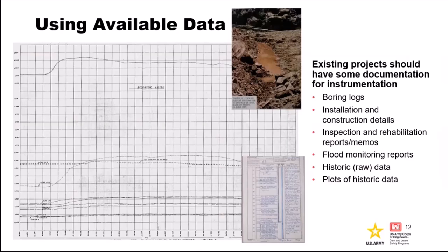We were missing field sheets that represented about a 15-year data gap at a project where we had a lot of concerns over seepage. And this was during first filling, so these were early performance records. I'm not certain if we touched on this, but historically speaking, in terms of internal erosion failure modes, most dams fail at first filling. So that early monitoring data is key.